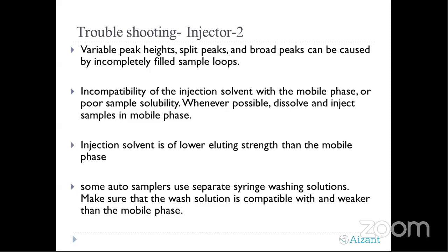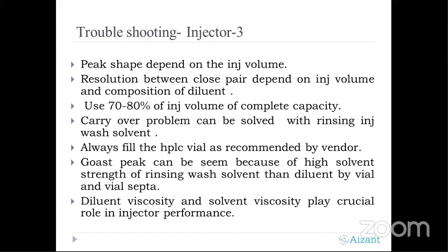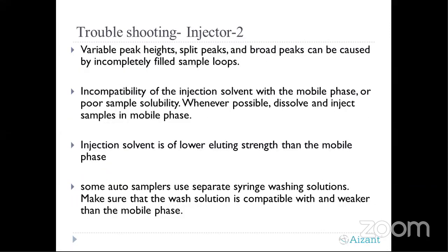I will give a simple example here. If you use THF in your sample preparation and you are using a mobile phase with more than 60 or 70% of either methanol or ACN, and your sample preparation is completely in THF, you will end up with a lot of challenges. First, the reproducibility of the peak will be a question mark, and the peak shapes will always be distorted. Either fronting will come or you will get a split, M-shaped peak.